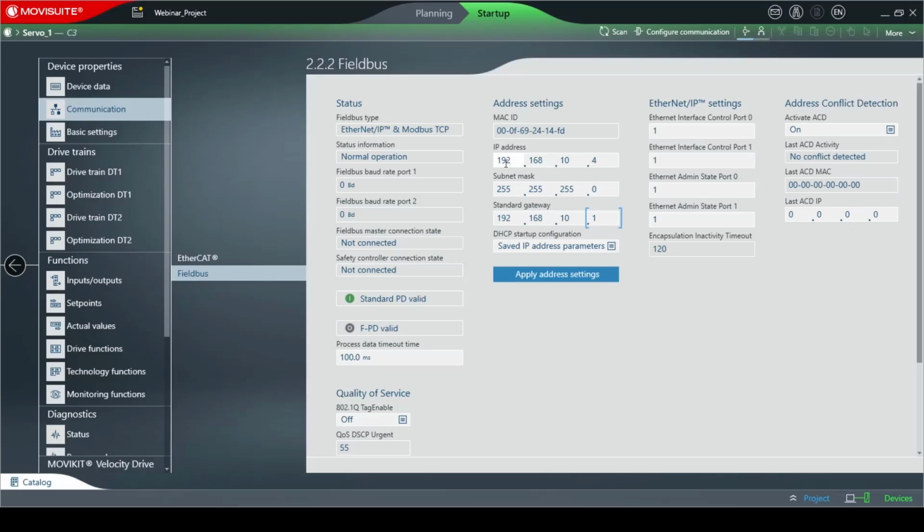Now if you do that, don't panic. It's not the end of the world. Just double check that your numbers are right. Hit Enter on that last digit, and if you've generated a fault, power cycle your VFD to clear it. Okay, this is a fault that you can't clear in the usual way through the software. You have to just power cycle it. So if that happens, don't worry, it's not a big deal.